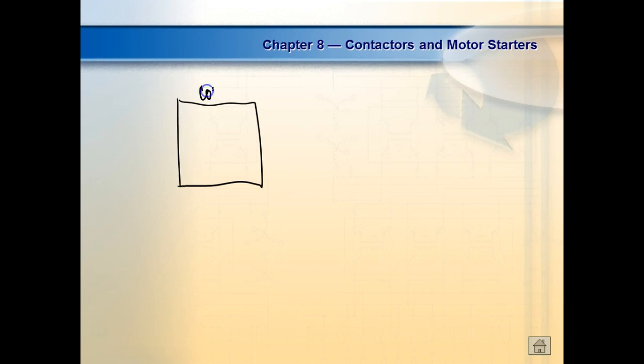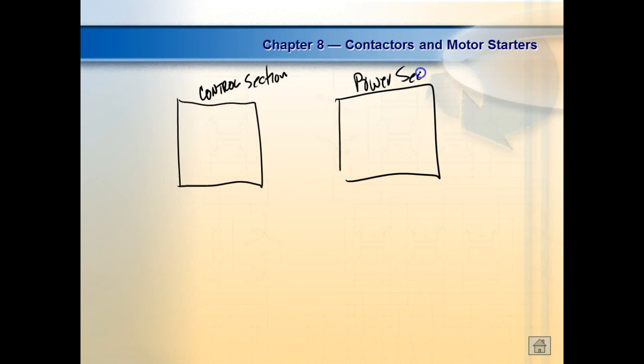So normally when you get into a control circuit, we're going to have two sections of the control circuit. We're going to have the control section, and then we're going to have the power section, right? Now the control section is going to be a relatively low voltage circuit compared to other voltages, right? The power circuit is usually going to be a high voltage circuit. So what advantage does high voltage have over low voltage? What's that? Less current to run a load.